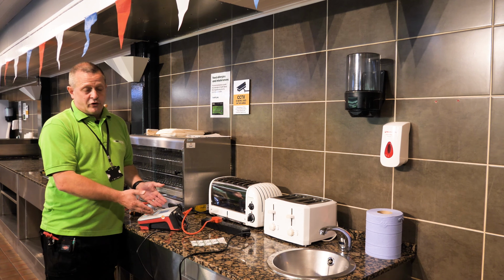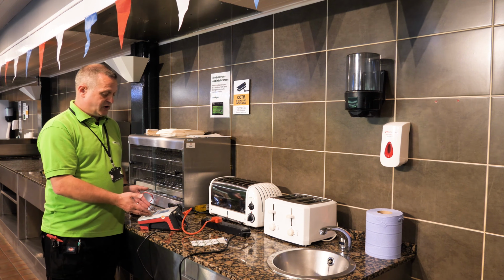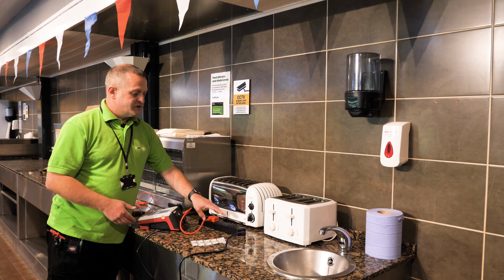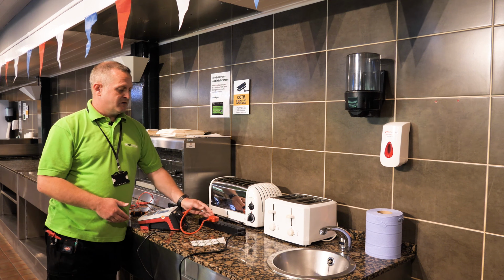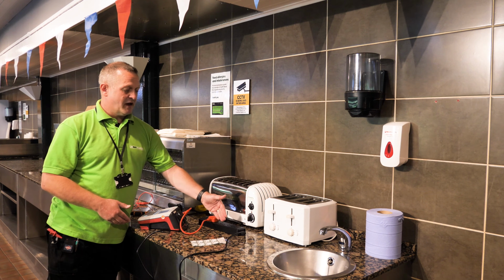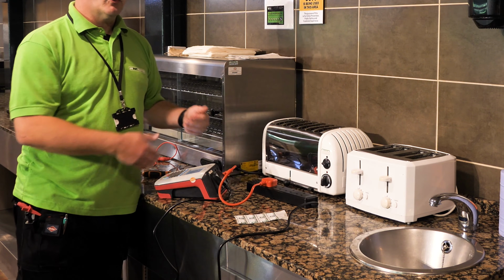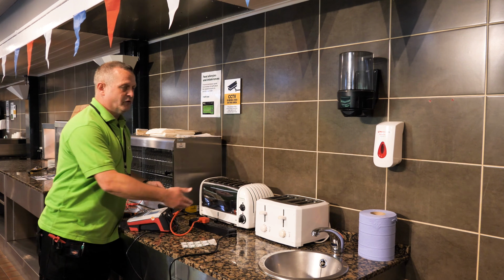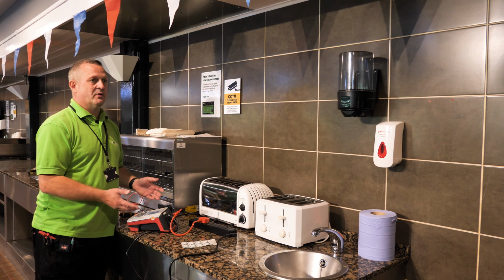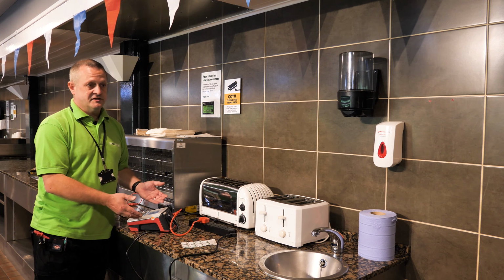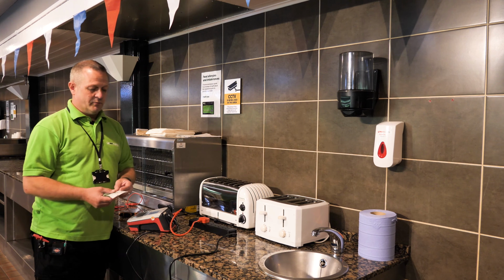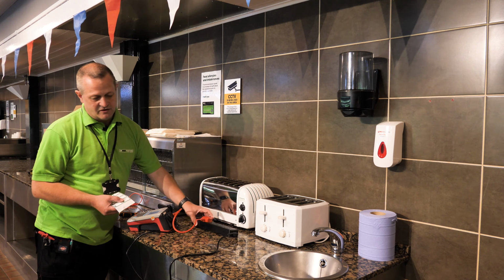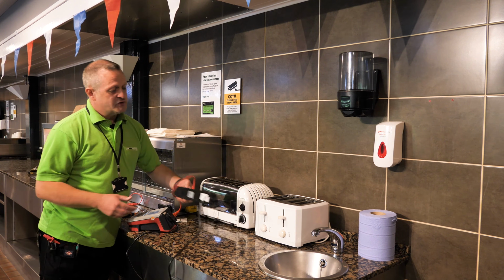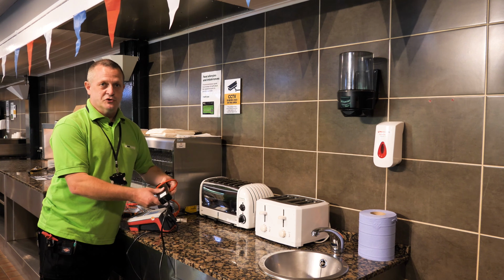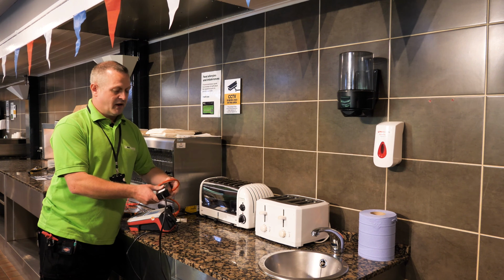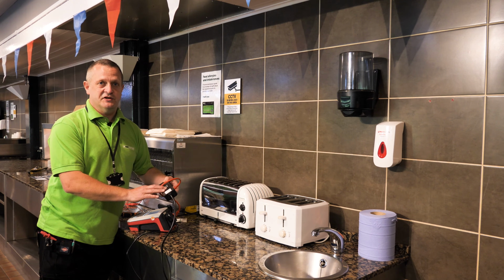It will then record the results onto the machine. However, what you need to do with the extension lead, there are 4 sockets, so therefore all 4 sockets need testing. So we will just repeat that process over 4 times to ensure that that appliance is in order, and then that is the test complete. We would apply our label in the most appropriate part where it's visible. And what we would first do is make sure that there's no dust or grease or anything where we're going to apply the label, so the label actually sticks.